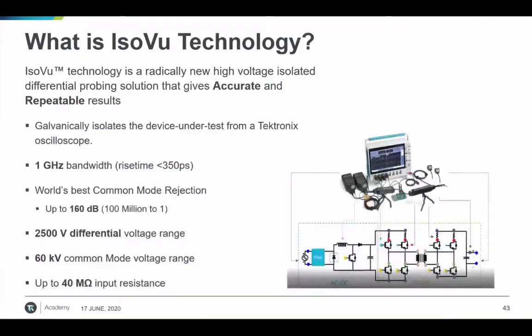The impact of galvanically isolated measurements is important because silicon carbide and gallium nitride semiconductors are being incorporated into many designs nowadays, featuring higher dV/dt, and making measurements on such devices has always been difficult — probes often lack adequate bandwidth and common mode rejection ratio specifications are not favorable. The IsoVu probe is very useful in applications with high common mode voltages, high-frequency common mode interference, or high EMI environments. Generally, all probes — whether passive or active — may have good CMRR at lower frequencies near DC, but as frequencies increase above 100 MHz into the hundreds of megahertz or gigahertz range, CMRR degrades very sharply and impedance drops, significantly affecting measurements.